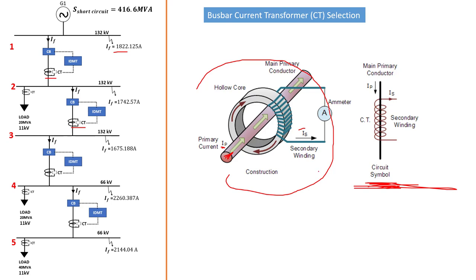Moving forward, the current on the secondary is directly proportional to the current flowing through the center of the core. The current flowing through the center of the core is Ip — our bus bar current. This secondary current IS is proportional to this current, so you just have to work in terms of the ratio. This one is going to be a small one. The number of turns here will determine how much you get here — that's where our turn ratio comes into the equations.